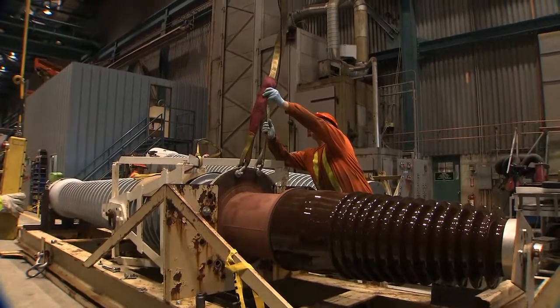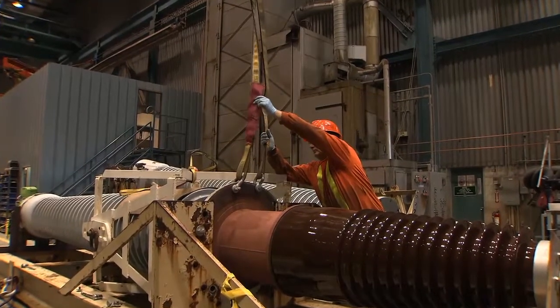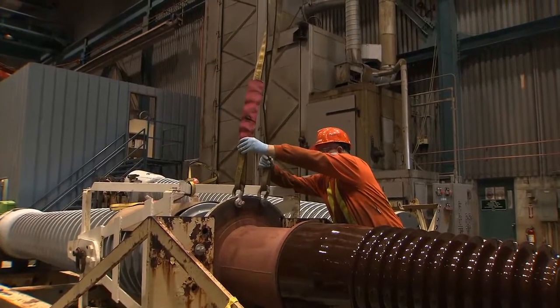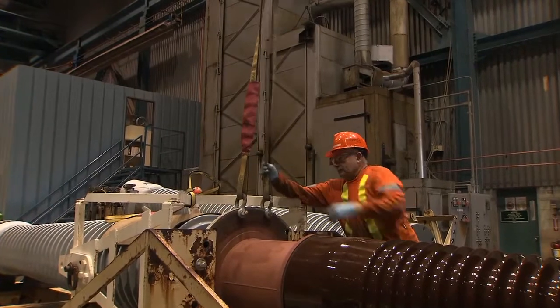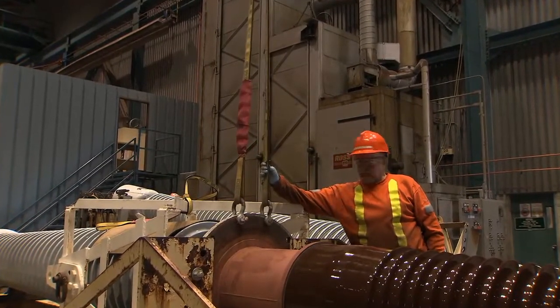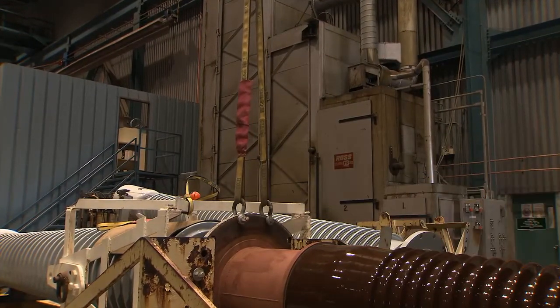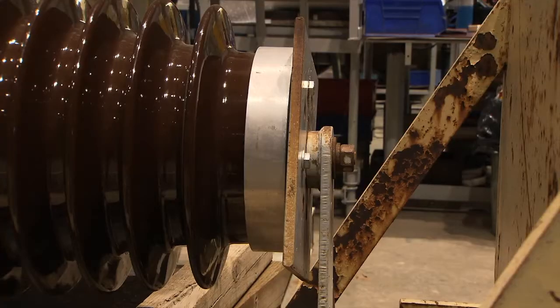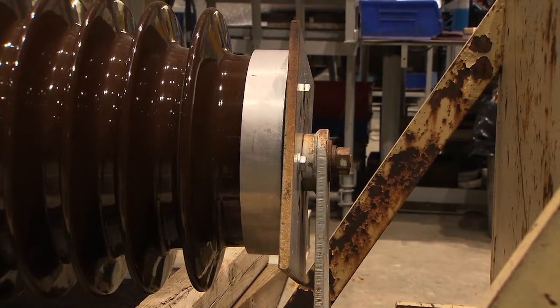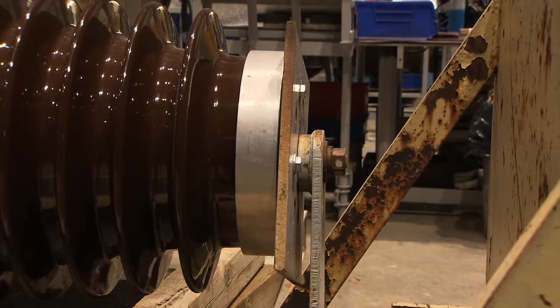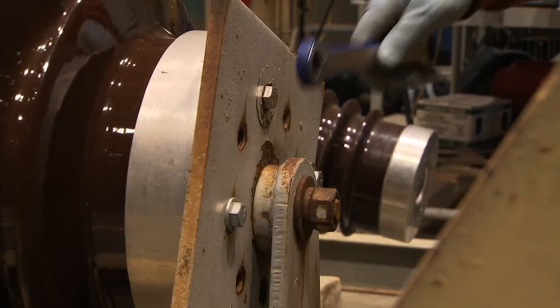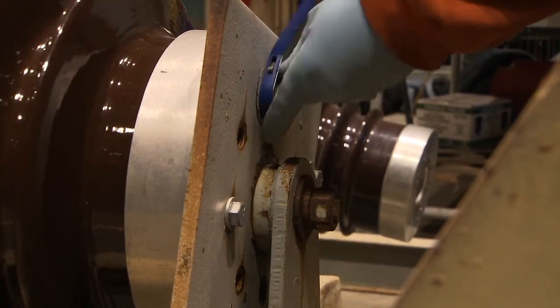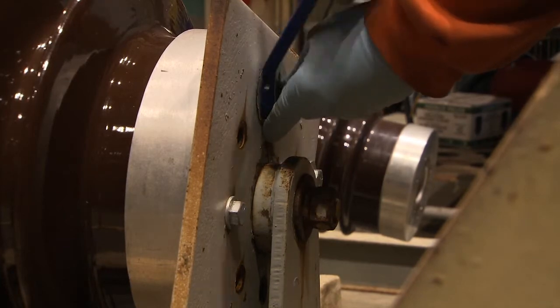After the slings are attached to the hoist hook, the crane operator can slowly raise the hook only to eliminate the slack in the slings. Prior to actually lifting the bushing, the bolts that attach the bottom flange of the bushing to a plate supported by a metal arm on the transport carrier must also be removed.